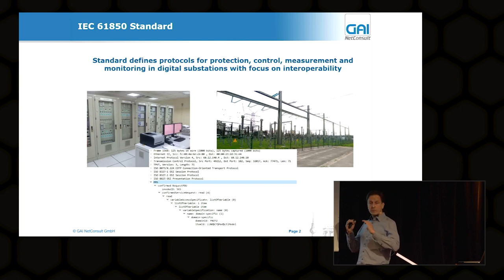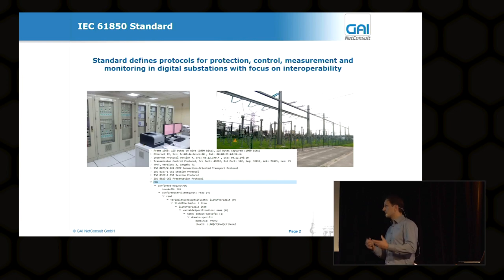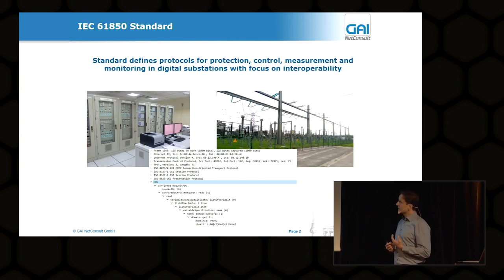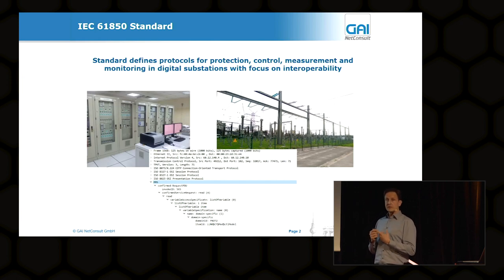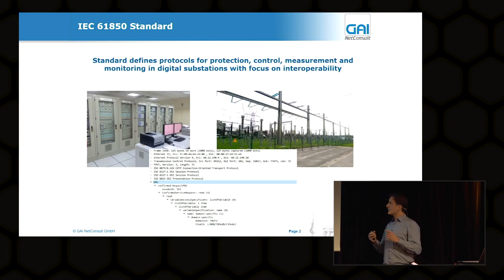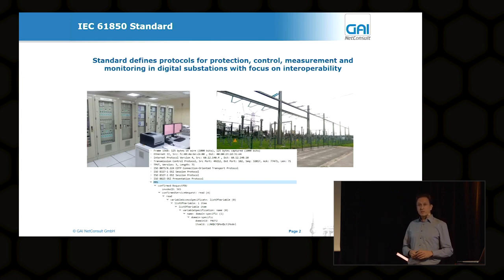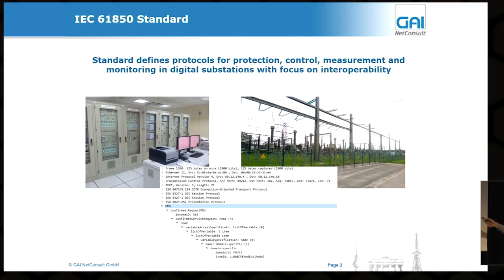What we can see is that in digital substations, our customers more often nowadays deploy the standard IEC 61850. Before, they had a bunch of protocols used in the substation, like IEC 103, 104, Modbus, or outside of Europe often DNP3. By deploying IEC 61850 they gain some main advantages: one single standard to integrate all protection, control, measurement, and monitoring, and the standard also has a focus on interoperability so devices from different vendors can talk to each other.